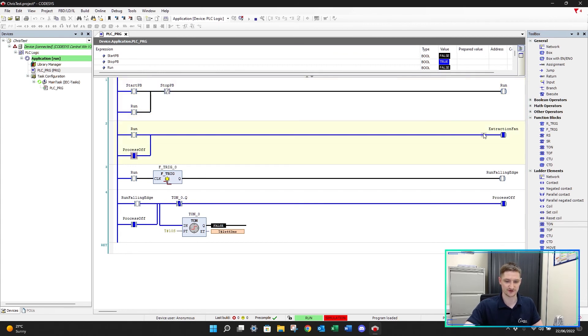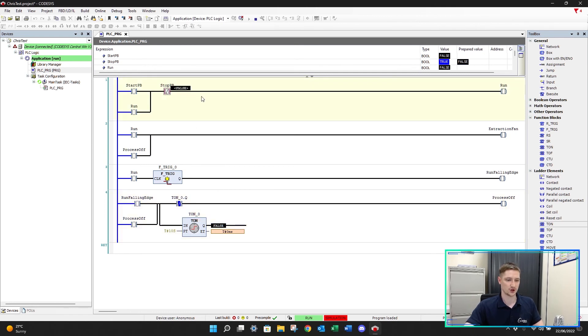This will blip for one PLC scan, latch on the 'process off' signal, continue holding the extraction fan on, and run this timer for 10 seconds. Are we ready? Three, two, one - Control F7. There we go. 'Process off' is now holding this on and the timer is running for 10 seconds. After 10 seconds the contact opens and everything goes back to zero. We're back to our base project.